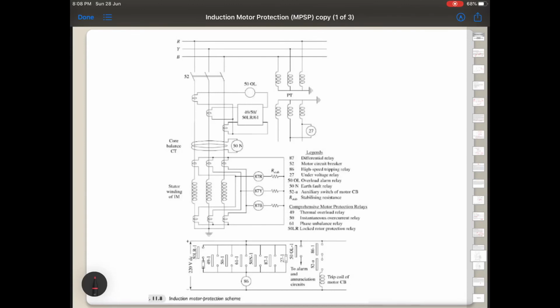Now we will also see the induction motor protection scheme. So this is the power supply, and this is the main circuit breaker, that is the motor circuit breaker. And here we have the alarm circuit and earth fault protection, the earth fault relay. And how the earth fault relay is implemented is something like this.